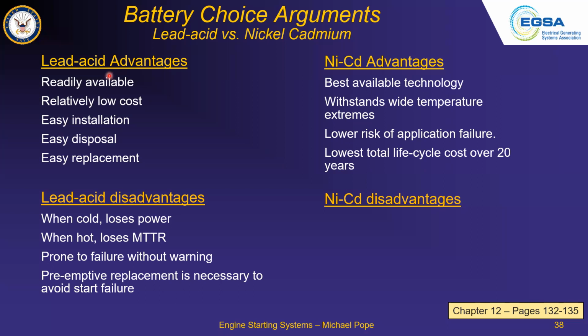You know, you think of those lead acid batteries being replaced every 2 to 3 years, and the cost of those versus the one-time shot of the NiCad battery. So under some circumstances, the cost can actually be lower. With many standby generator sets, the total life cycle cost is not of concern - it's got to meet the spec, it's got to be cheap.